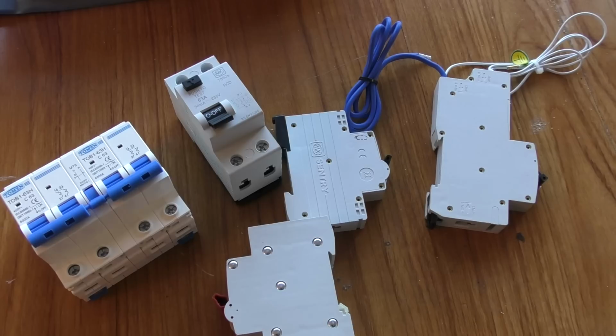But a consumer unit is basically a tin box with some breakers in it, and it's a standard DIN rail breaker. Everything's the same mechanical standard. These days, generally the bus bar heights are the same. So although it could be argued that putting a different manufacturer's circuit breaker in there isn't strictly compliant with the regulations, I think it would be very hard to argue that it's a safety hazard, or that it would, for example, fail an inspection.